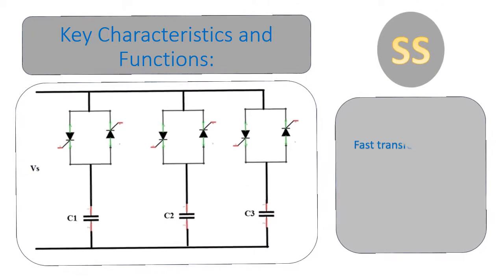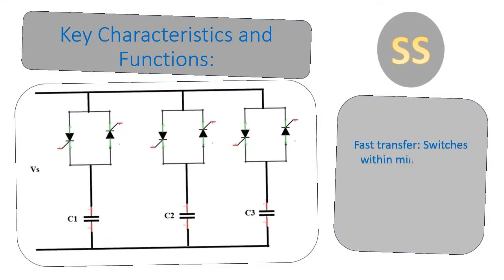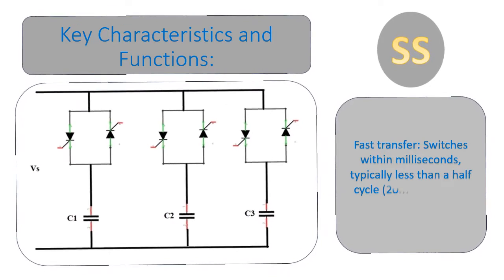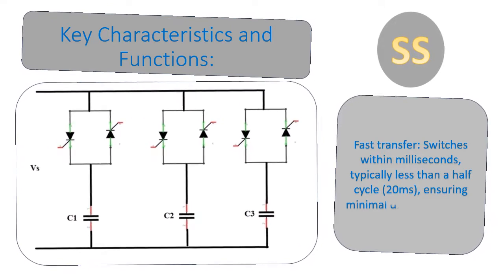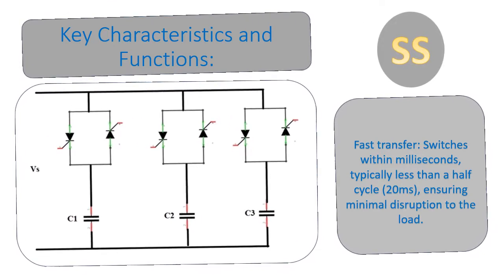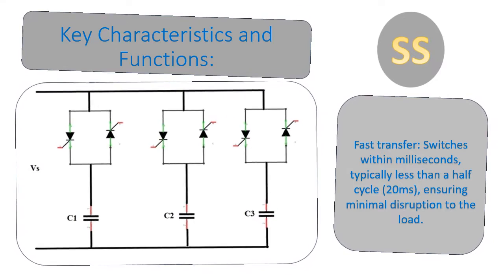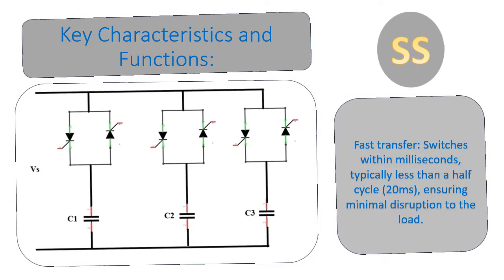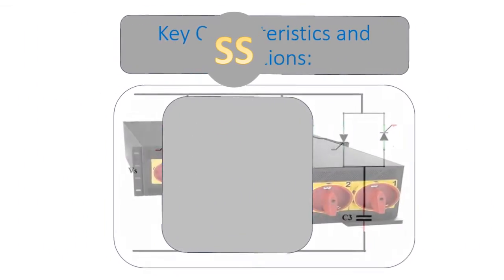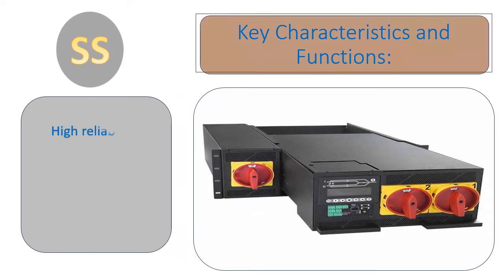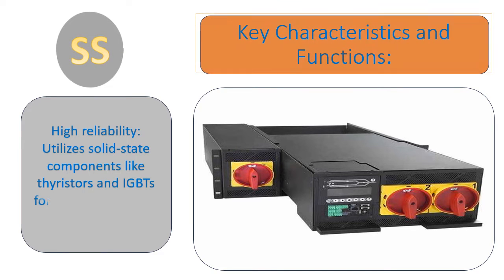Fast Transfer: switches within milliseconds, typically less than a half cycle (20ms), ensuring minimal disruption to the load. High Reliability: utilizes solid-state components like thyristors and IGBTs for reliable and long-lasting operation.